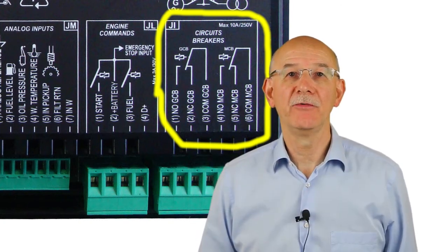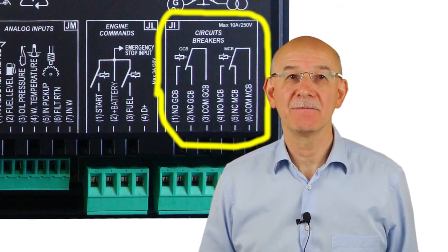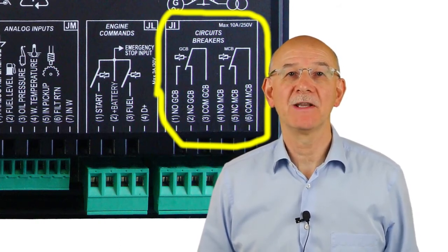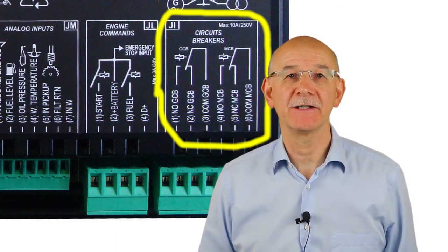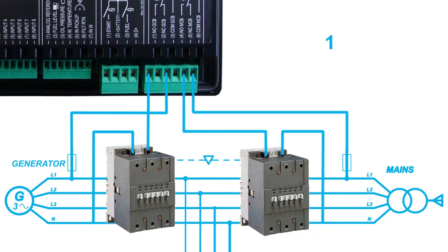A digital output configured for stable mains circuit breaker command using function 2004 is activated in order to open the MCB. Thus, the normally closed contact of the relay should be used in order to command the breaker. The advantage is that in case of controller power off, the MCB is automatically closed. In any case, you can reverse the operation by the checkbox to reverse functionality.